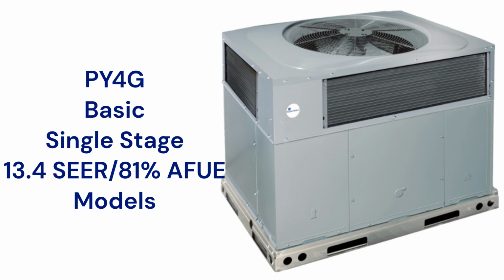They use a wire mesh protection for the condenser coil, which doesn't do much as far as protecting the coil, and R410A refrigerant, which is not as environmentally friendly as R32. The units use direct spark ignition, which is not as reliable as brands that use hot surface ignition.